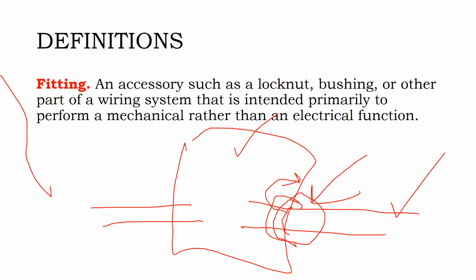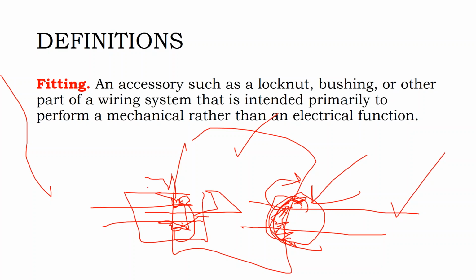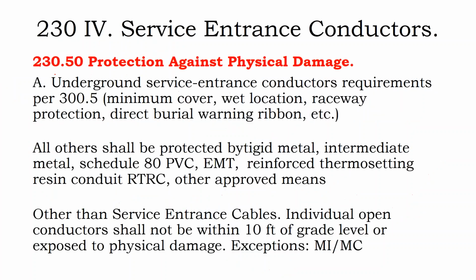metal conduit to the box, or if you're just using the non-concentric dedicated outer perimeter knockout and completely filling it up, at which point you may just need a lock nut, which is kind of like a jagged washer that goes around, plus maybe a threaded fitting, and then a bushing to go over the threaded fitting so that your cable and your conduit isn't rubbing on any sharp edges. So you might have 3 or 4 pieces that attach this conduit to this box. They're all called fittings. And generally, general electric contractors know what to do with fittings. These are your Home Depot items that are commonly found off the shelf.